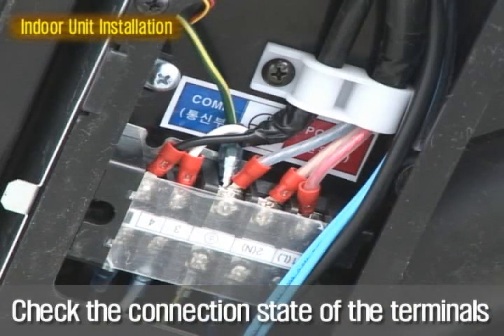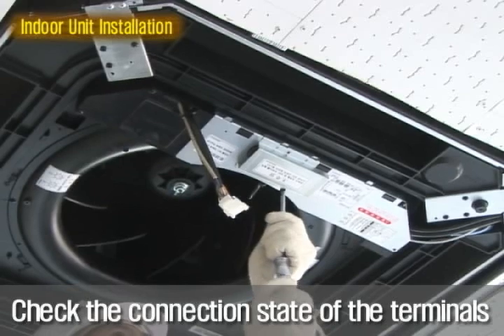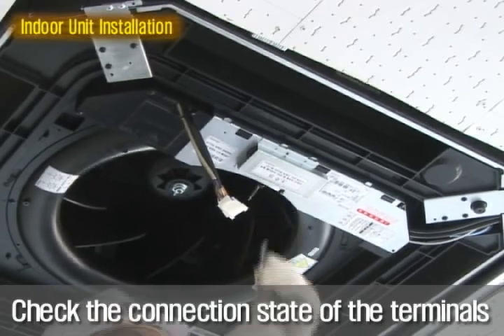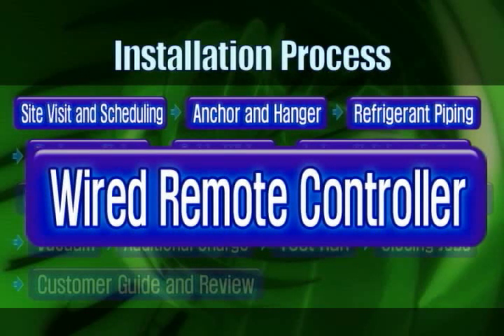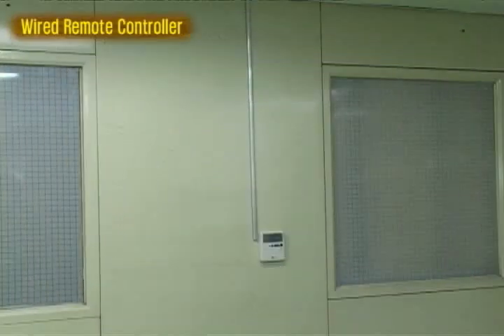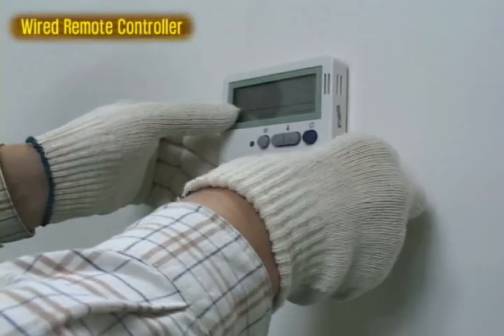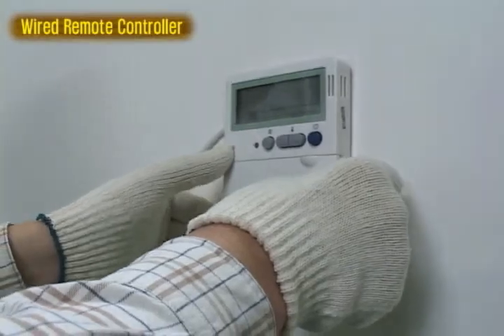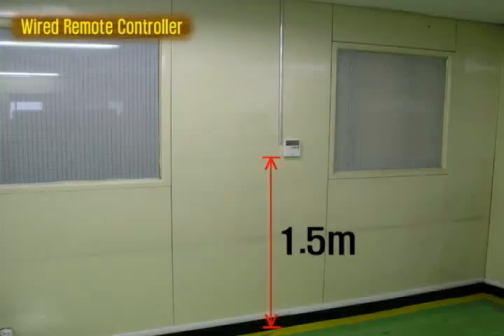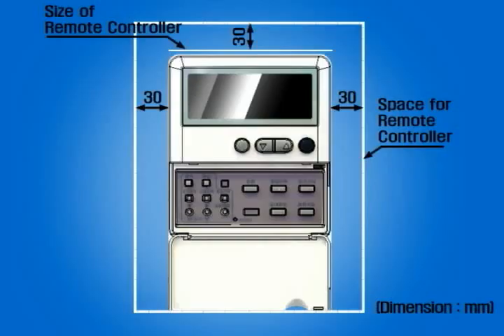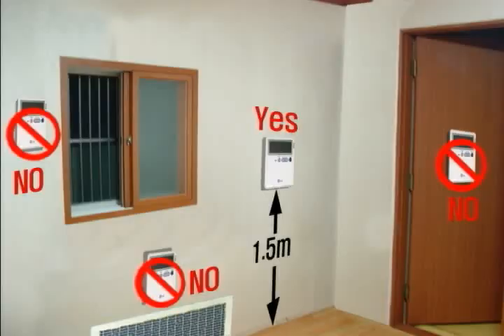Connect the wired remote controller. Arrange and fix cables with cord clamps. Then fix the control cover. You must install wired remote controller for ceiling cassette, low and high static duct products. Wired remote controller should be installed to detect average room temperature at 1.5 meters height and have minimum space of 30 millimeters each direction from the controller for cover open state. The following spaces should be avoided.